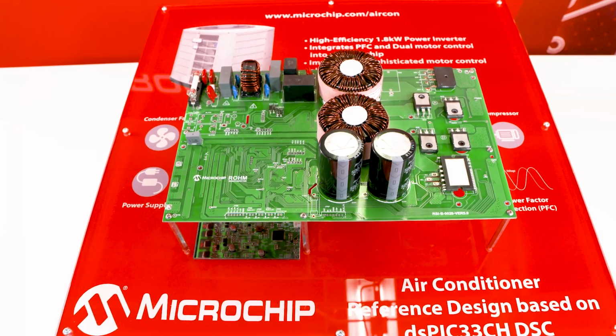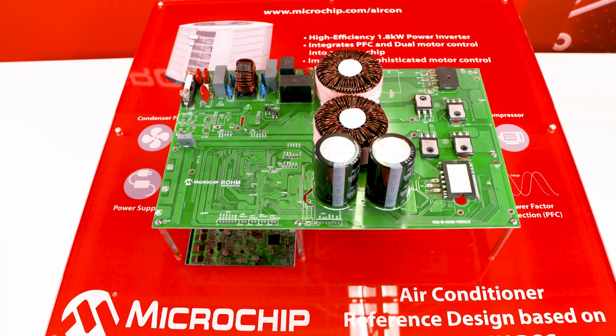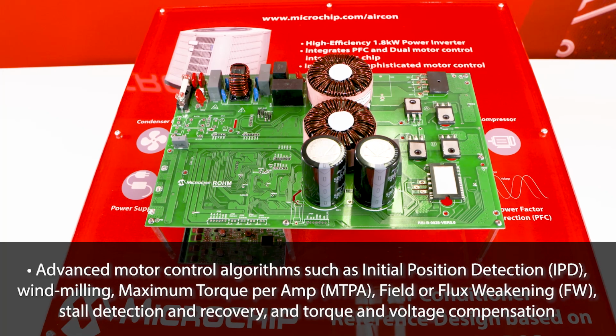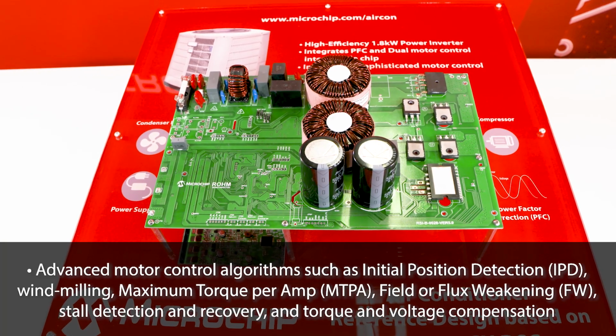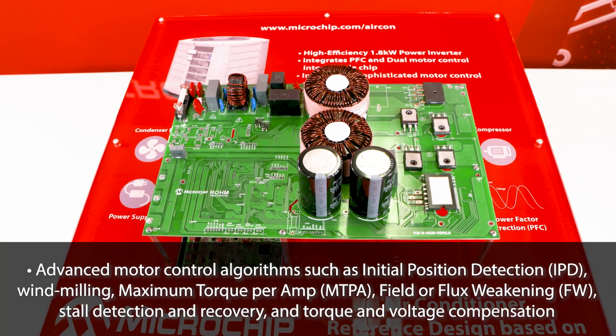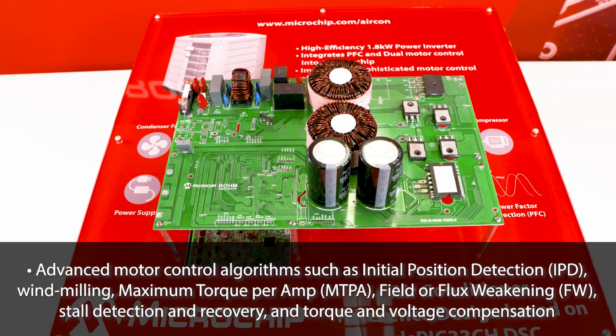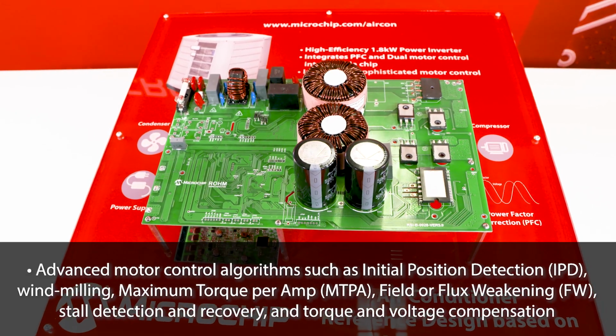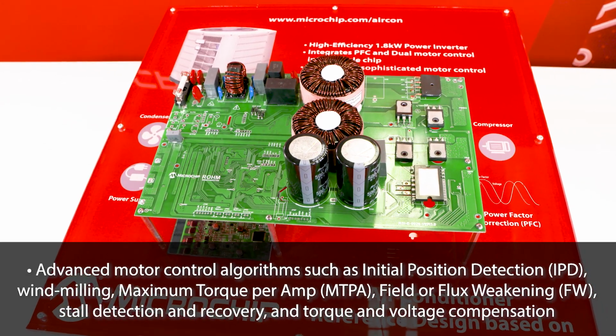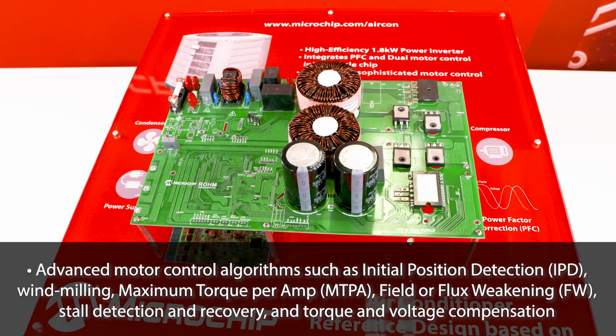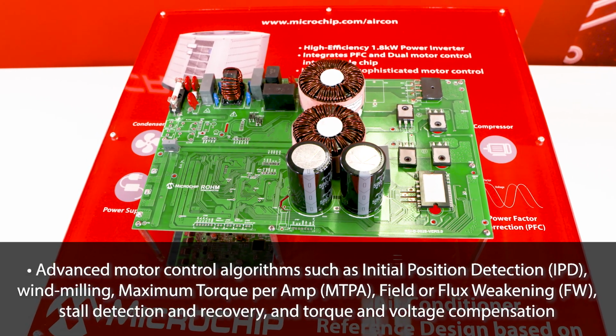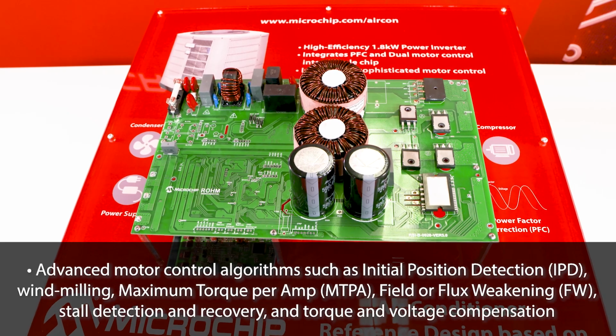The reference design software also implements many advanced motor control algorithms, such as initial position detection, windmilling, maximum torque per amp, field or flux weakening, stall detection and recovery, and torque and voltage compensation, in order to improve the startup or the operation of the fan and compressor motors, and also to increase their efficiency.